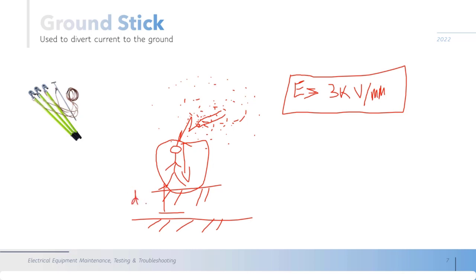But if this distance is also not enough to isolate this area from these 3 kV per millimeter, because you are also energized with the line voltage when you get this charge, so if the distance does not create a sufficient minimum distance, the air in here will also be disrupted and you will discharge your energy to the ground. So the line will be discharging to you and you will be discharging to the ground. This is why we use ground sticks.